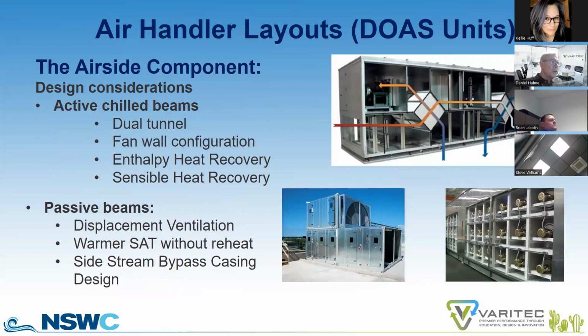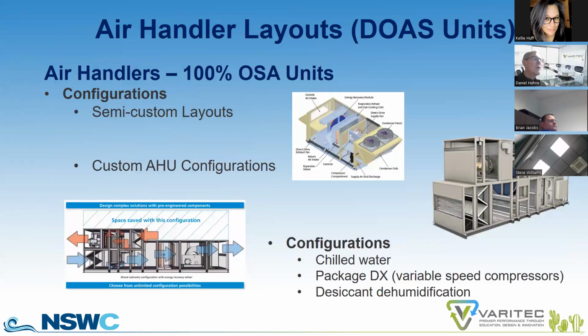And here are some considerations that give you an idea of how these dual tunnel units look like. Fan wall technology is certainly available, so we can optimize fan performance, heat recovery across a coil that is always seeing a uniform velocity across the full coil face. And a lot of solutions we can do with air handlers. And again, there are semi-custom configurations, custom configurations, different price points that we would see. Traditionally for chill beams, we would see chill water, but I think we might even want to consider looking at packaged DX solutions with variable speed compressors. And the reason why I say that will be addressed here shortly.